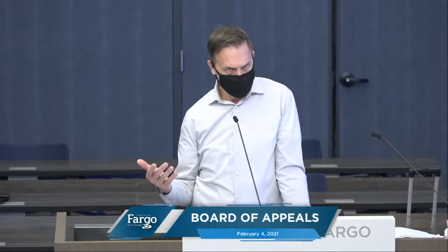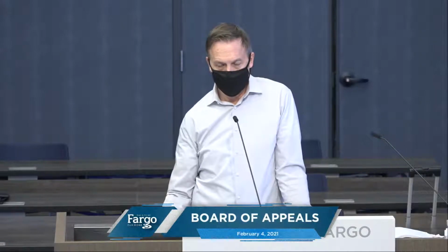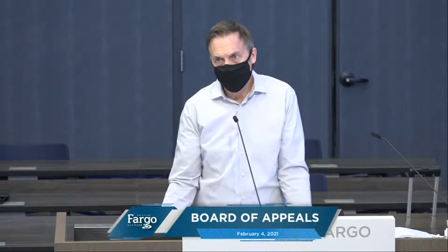In this case, we could look at it. IBC 104 allows us to look at any option as a compromise to some issue that might allow us to see the intent of the code met. Could you look at it as an alternative to one-hour construction? Yeah, because we do that all the time with window systems that have a deluge system, where you're basically eliminating the one-hour requirement for the window.